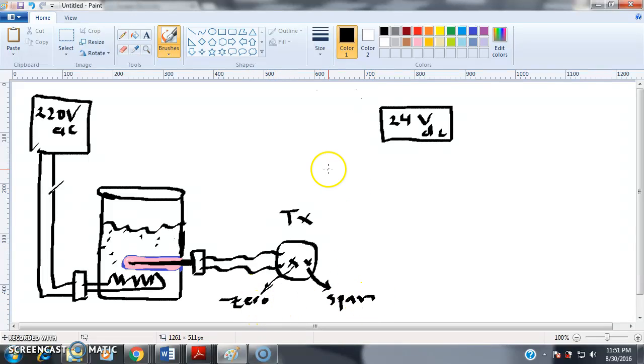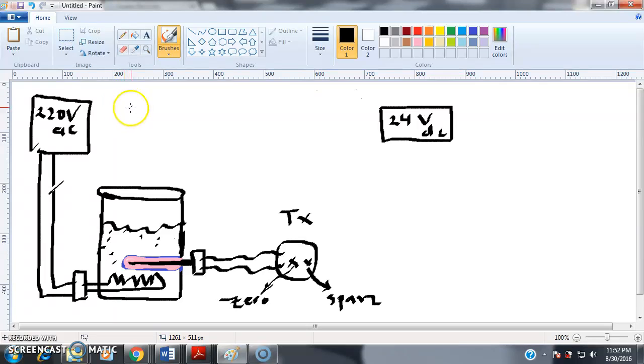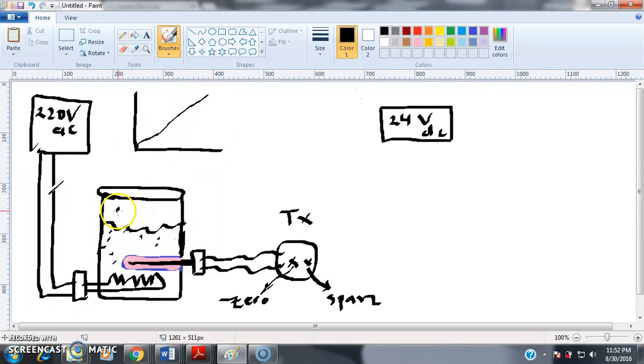The purpose of the Zero pin is for low-range calibration, and the purpose of the Span pin is for high-range calibration. For example, at room temperature the water in this tank might be 24 degrees Celsius, and if the maximum temperature in this tank is going to be 100 degrees Celsius, then the range is 24 to 100 degrees.